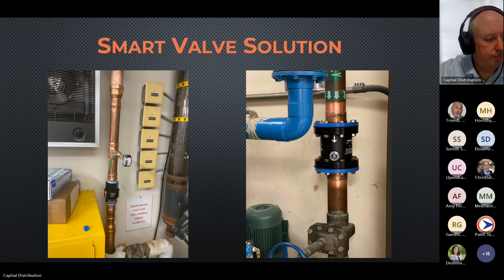So how does the Smart Valve work? That's the big question. What the Smart Valve does is essentially act like a toll booth. It's going to maintain the pressure between it and the meter at a constant state. Typically, you have pressure coming in from the street. Anytime there's a demand, a few things can happen that can cause some chaos on the line. One, you can get a large demand. If you picture an apartment complex, again, as an example, or a hotel, a lot of places like that, you might get a lot of people showering early in the morning. So you have a high demand.